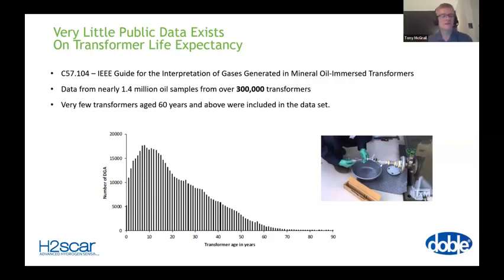I would like to go back to something Moses said about qualified workers. And it is relevant here that to take a good oil sample to generate data to assess the condition of your transformer and then make a decision about that transformer needs someone who knows what they're doing to take a sample. And not only are they qualified to be on the site, not only are they qualified to take a sample, but when they take a sample, or they run an SFRA test, or they run a PD test, can they recognize data which is acceptable? Irrespective of how you interpret it, can you actually recognize that you've made a good reading before you try and work out what the reading means? And that to me is what a qualified worker is. They can identify an SFRA trace and say, yeah, it's what we'd expect. Now we'll try and interpret it. So just as an aside, thank you, Moses, for pointing that out.